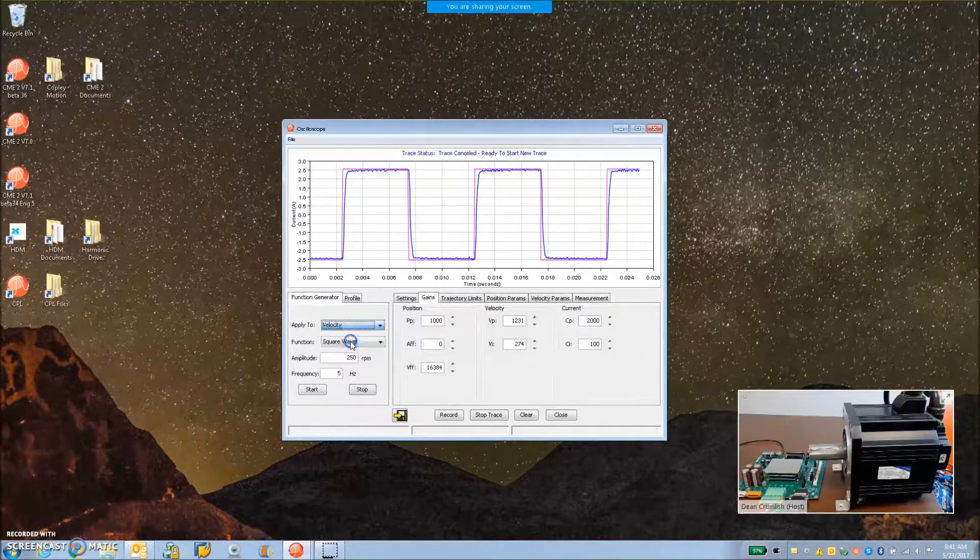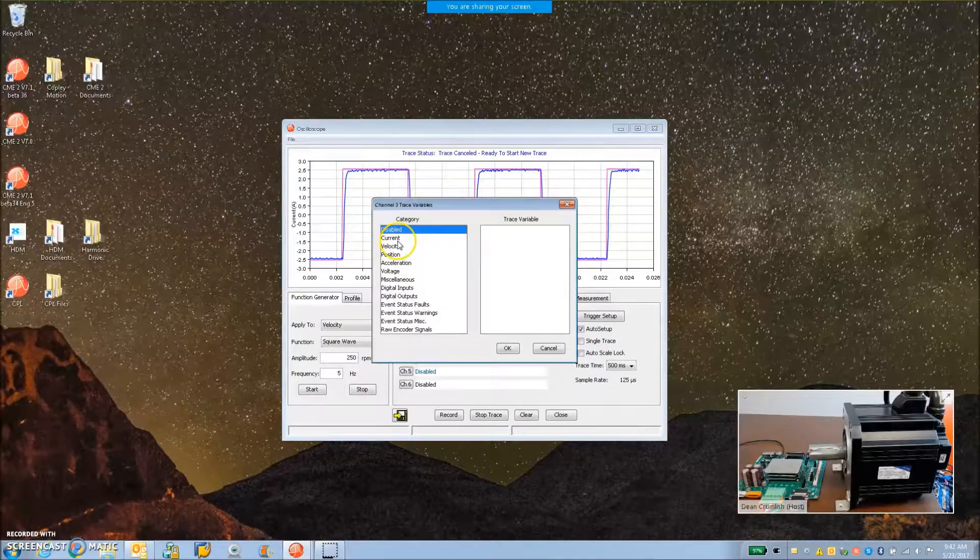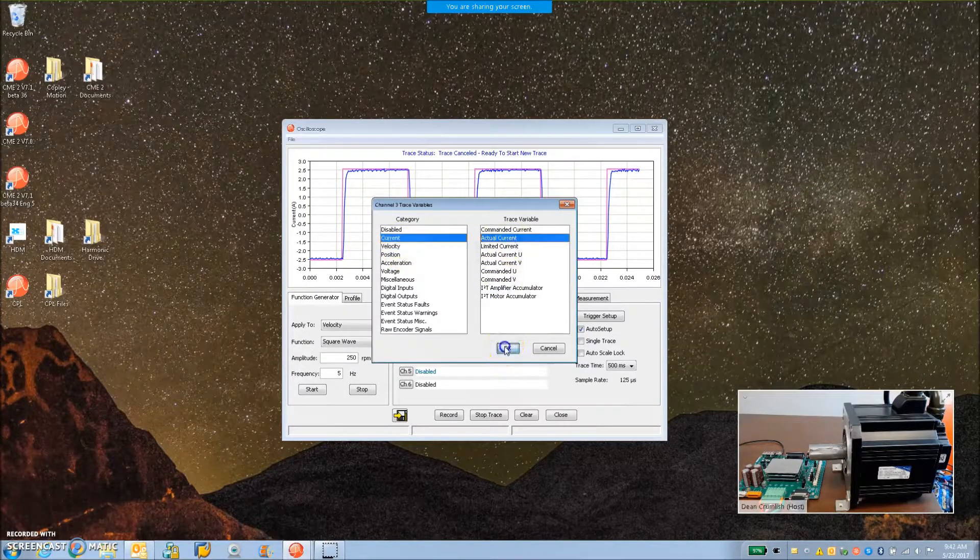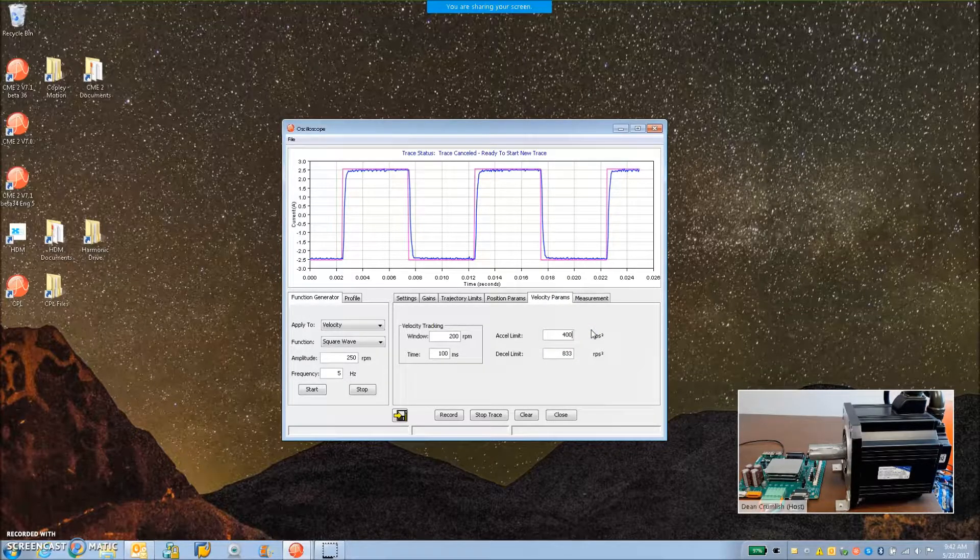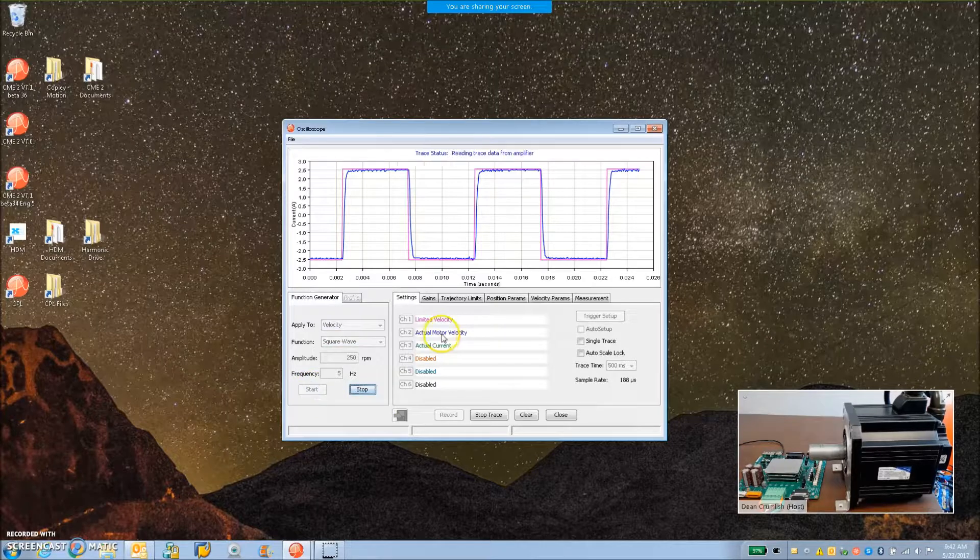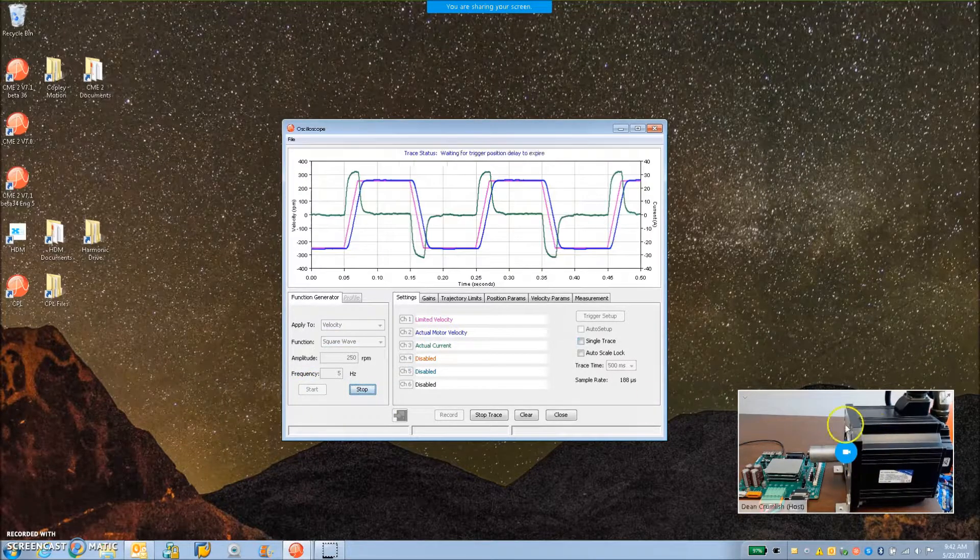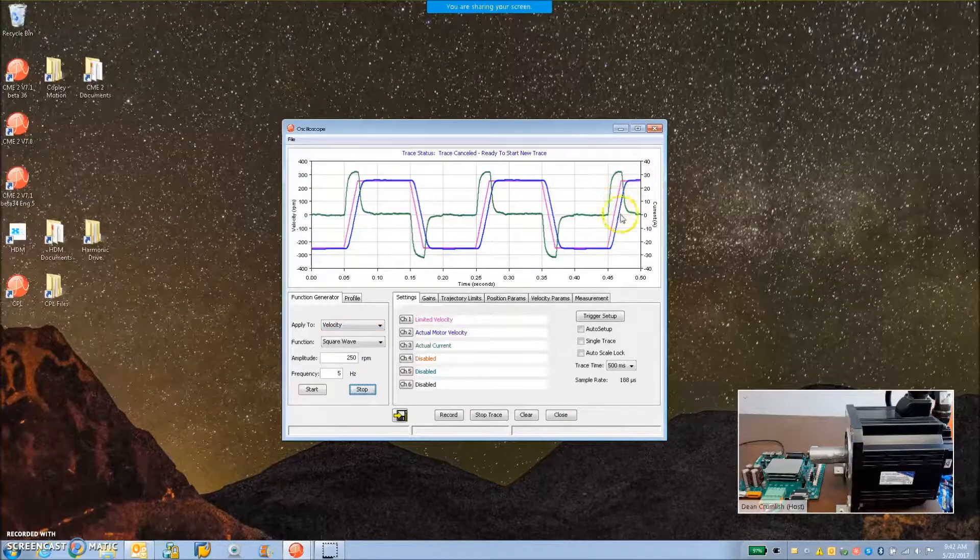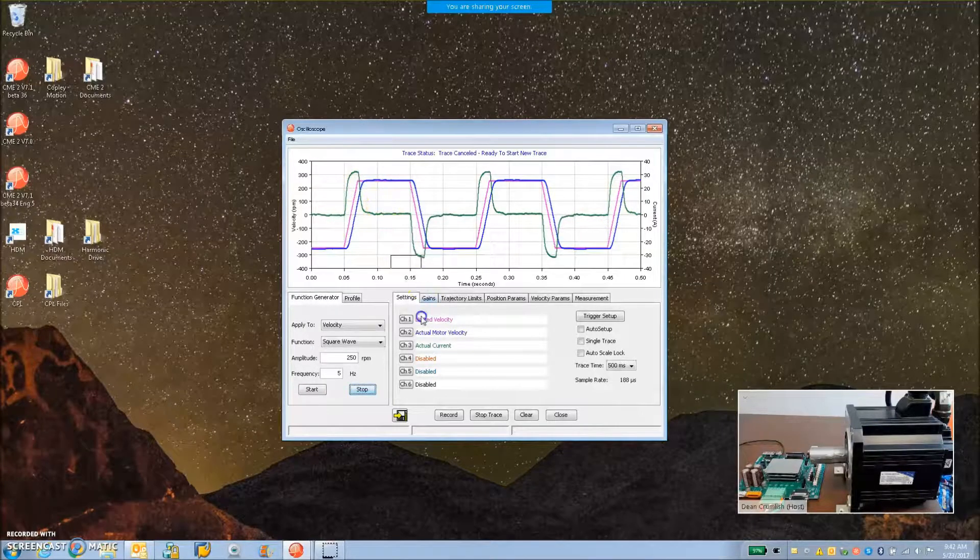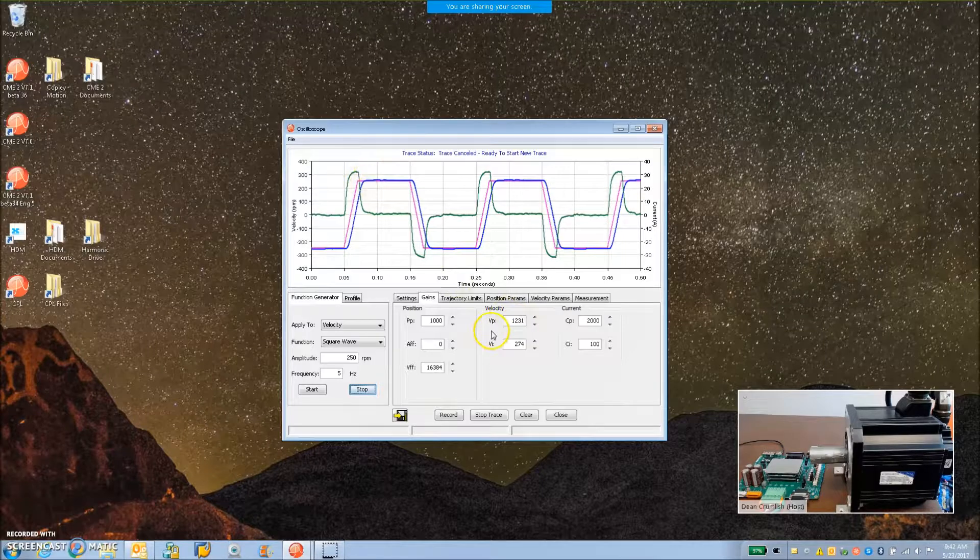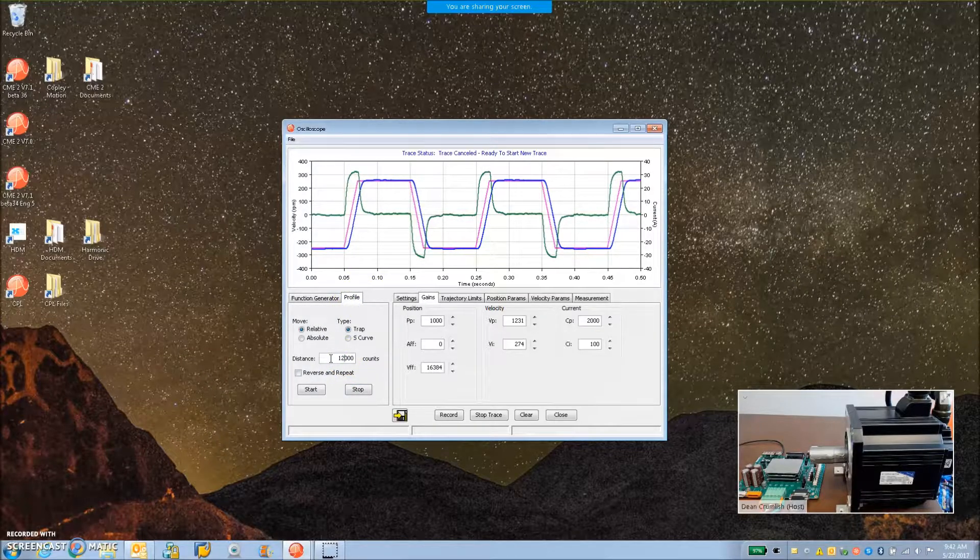I'm going to do the velocity auto setup checkbox. I'm going to take a look at the current, actual current. And don't go too crazy with the accel and decel, so this will give us a little more reasonable accel and decel. Still bangs back and forth here, it's rocking, so we can take a look at the, yeah hitting 30 amps already for acceleration. The command and actual look pretty good. We can mess with the gains again, crank up the P to get overshoot, then the integral. I'm gonna leave this alone because it looks pretty solid, skip right to making a...